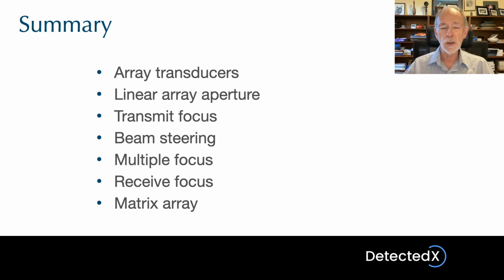I talked about receive focusing, which is very similar to transmit focusing. The received echoes from the elements are delayed and then combined together in a way that focuses at a specific depth. Receive focusing, though, can be dynamic because at any one moment the machine is receiving echoes from a known depth, and therefore it can adjust the delay elements continually so that it is always optimally focused while it's receiving. And then I showed you the matrix array transducer, which is cut up into elements along its length and across its width.